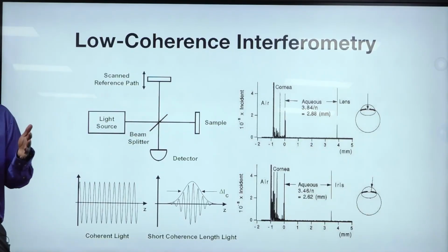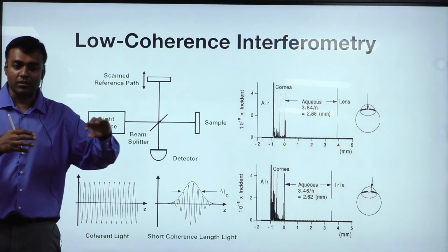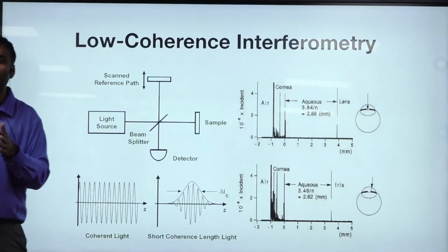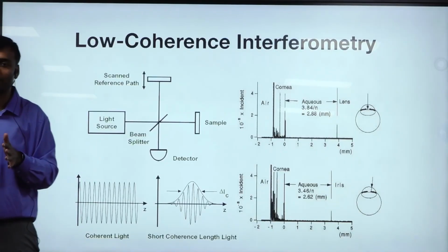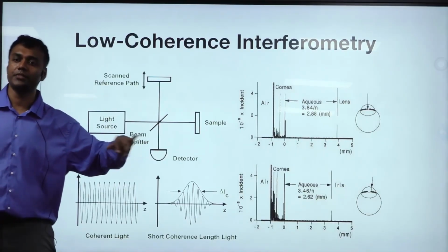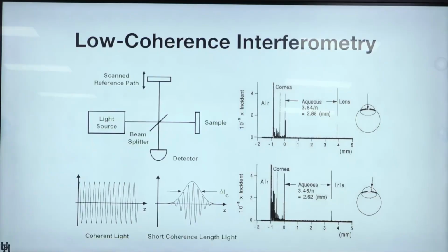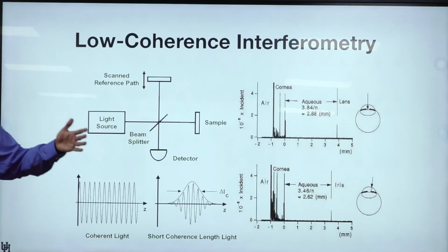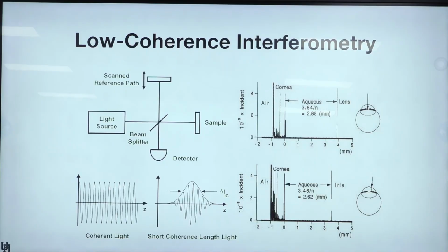And if you have another wavelength, only at the 0 position will all wavelengths interfere constructively. They will wash away, destructively interfering at all the other positions. That is exactly why you can't use a narrow band or one wavelength for OCT. That's the reason why you need light which has a large range of wavelengths. In fact, the more wavelengths you have, the better.